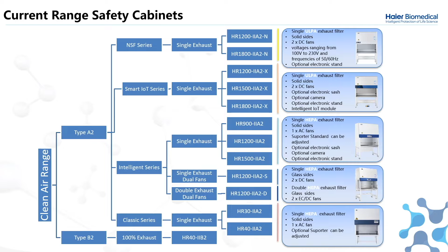An important thing to understand when selling the products is the part codes and how they're laid out. The start of the part code refers to the type of cabinet, so HR being microbiological safety cabinet, HCB being laminar flow. The number after that is the working width, which is not to be confused with the external width. The working width is just the area the user has to work in. After that, you have the airflow circulation. So II-A2 refers to a Class 2 with A2 recirculation, which, as I mentioned before, is 70% downflow, 30% exhaust.